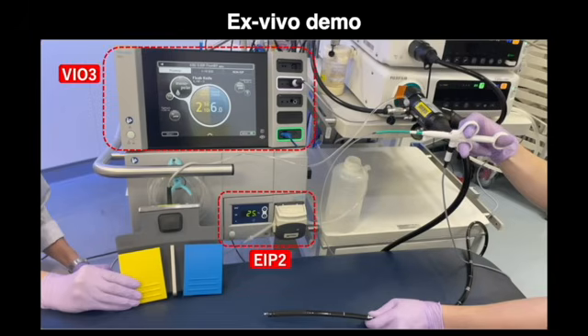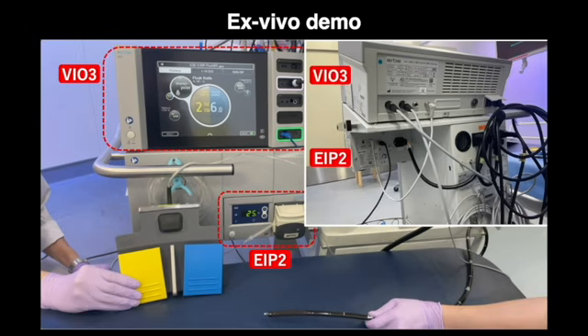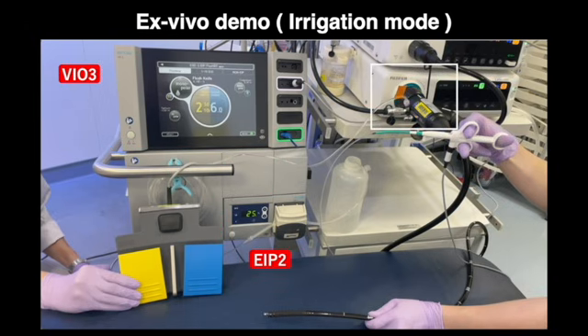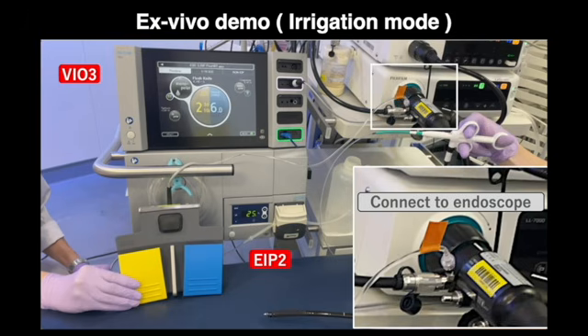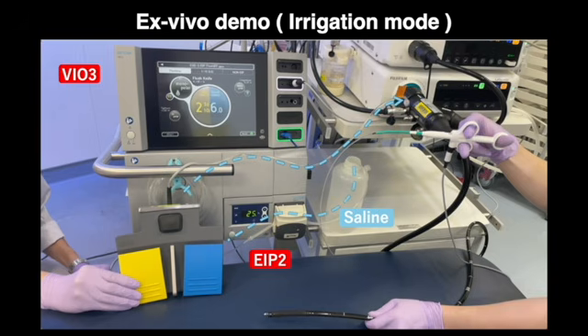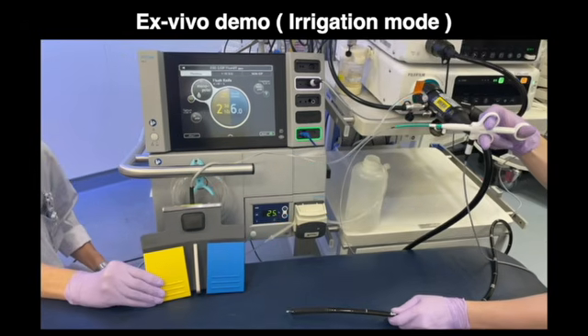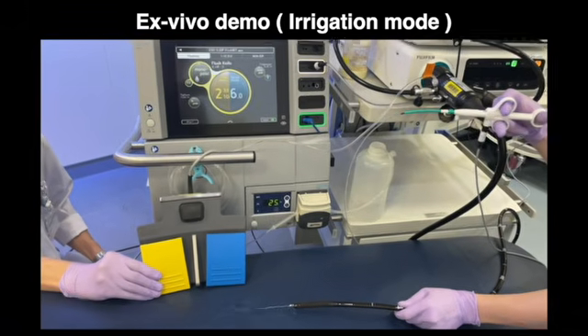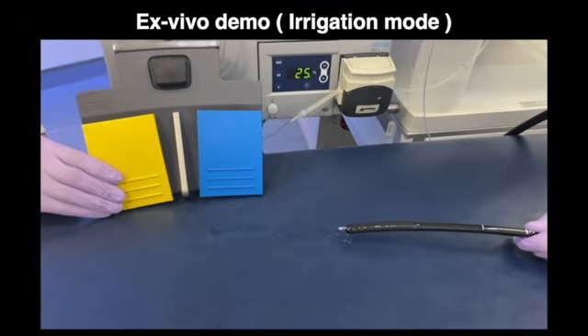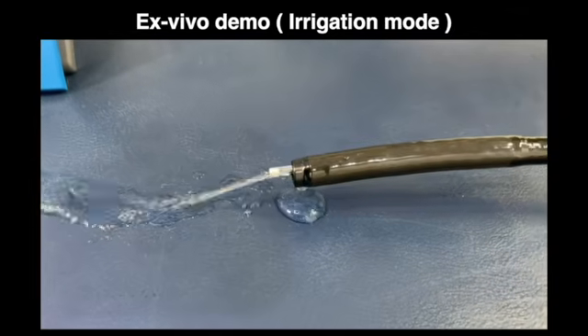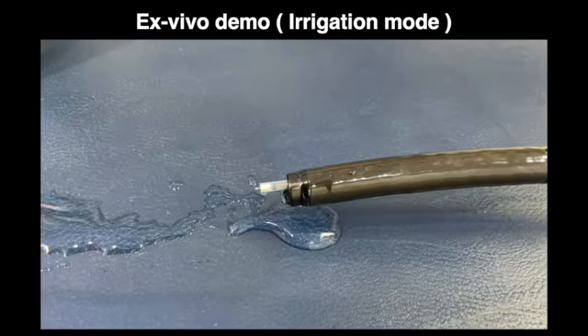We will now provide an ex vivo demonstration to better clarify the overall system setup. First, the electrocautery unit and irrigation pump are connected via a dedicated interface cable shown here. This allows the two devices to operate in synchronization. Next, we will demonstrate the conventional irrigation mode. In this mode, the irrigation pump is connected directly to the endoscope. When the operator presses the electrocautery pedal, there is simultaneous discharge from the knife and saline jet from the endoscope.